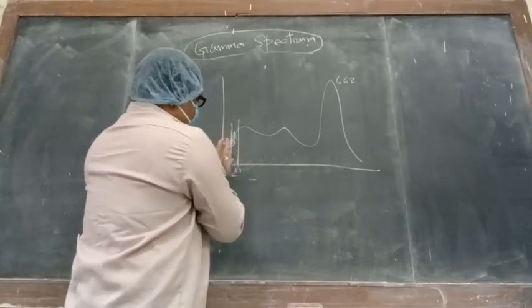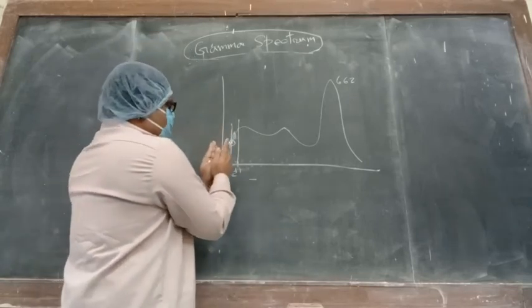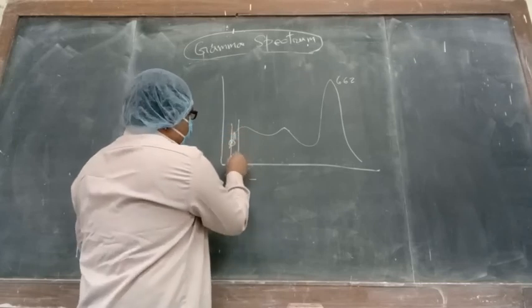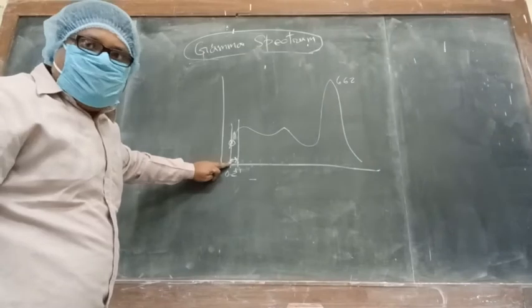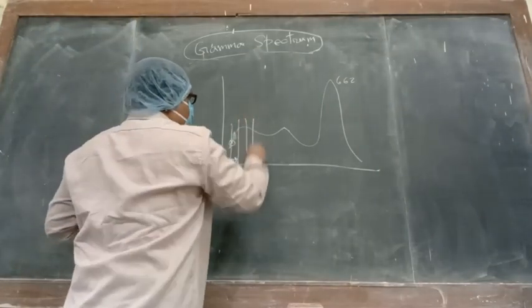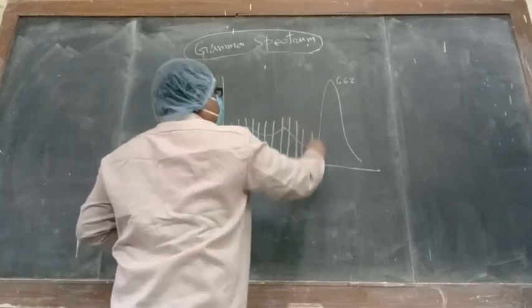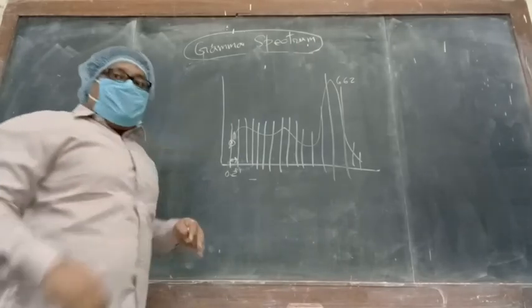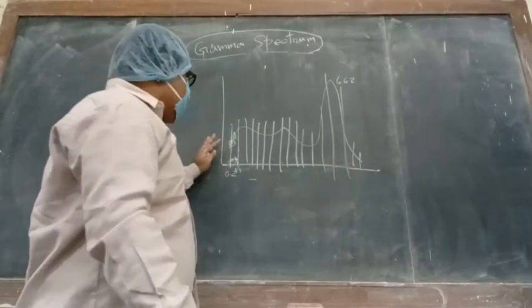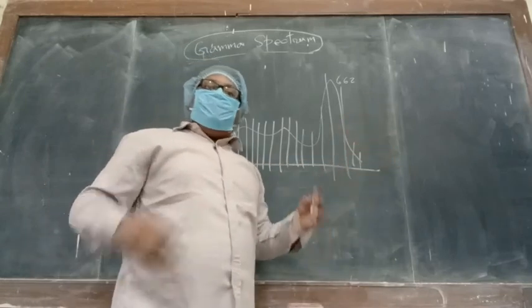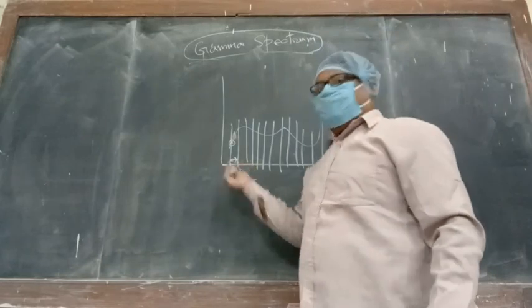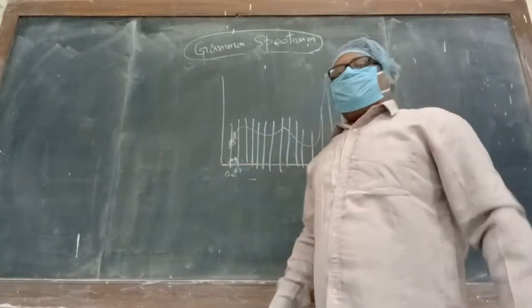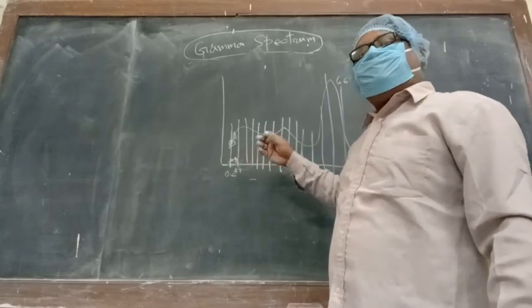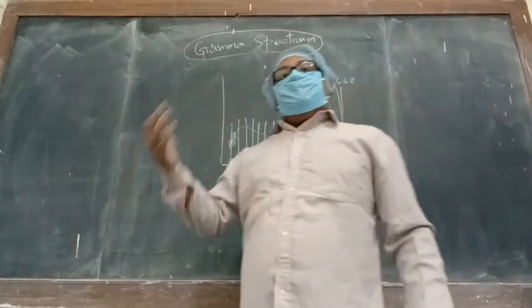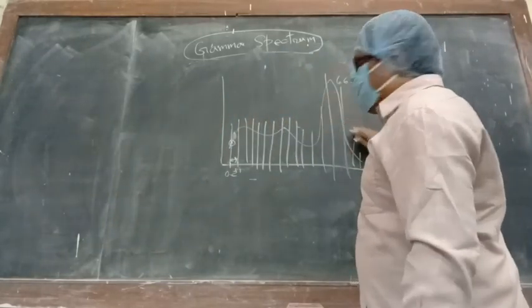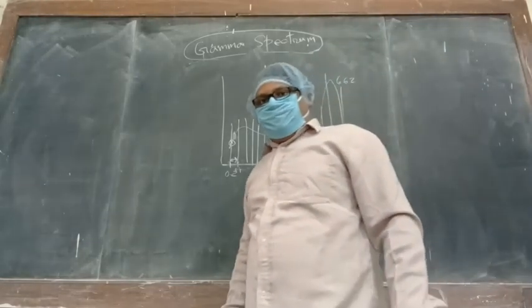So this is the baseline voltage, that means the lower limit of the discriminator. We are just changing it, and the upper limit we have set at a fixed value from the lower limit, say 0.2 volt. By doing so, we will be taking the data in terms of energy bins. If we use the multi-channel analyzer, everything will be taken instantaneously. In this experiment, we are taking the data at each point for say 30 seconds. In the multi-channel analyzer, if you take the data for 30 seconds, you will get very few counts. But if you let it take the data for say 1 hour, then only you will be able to observe the whole spectrum. Okay? Fine.